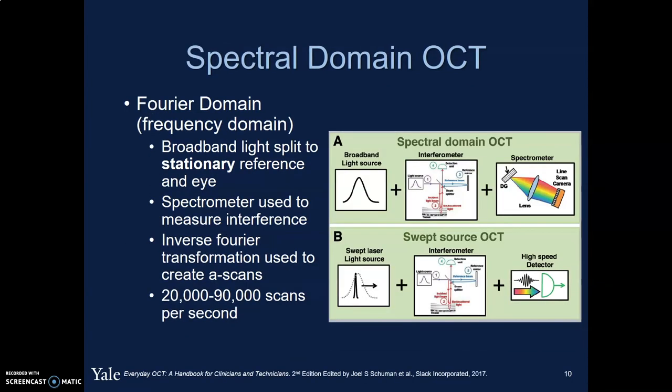The next generation was spectral domain OCT — a frequency-based OCT. It uses a broadband light source, but it's now split to a stationary reference arm as well as the eye. Instead of a mobile reference arm, it uses a spectrometer to generate interferences and an inverse Fourier transformation to create the various A-scans that are put together to generate the pictures we see. Because it's no longer dependent on a mobile reference arm, it can do 20,000 to 90,000 scans per second.